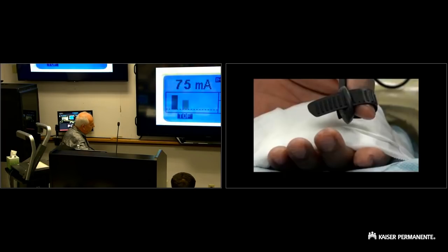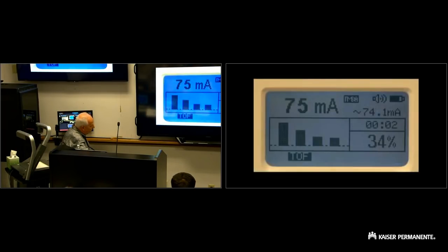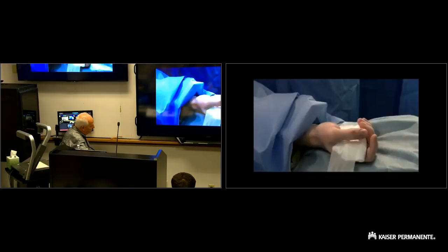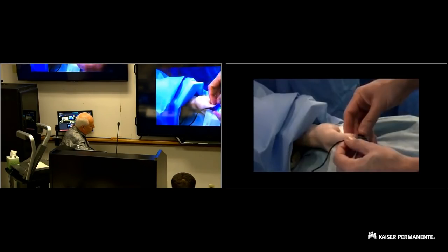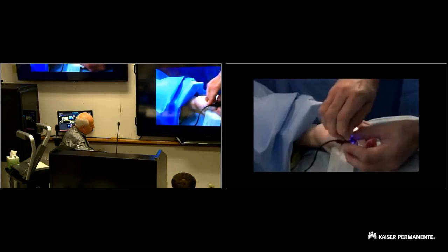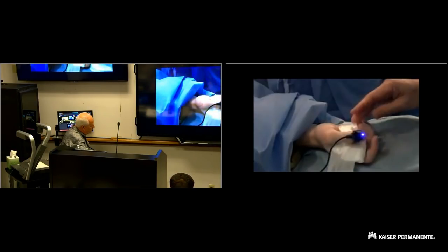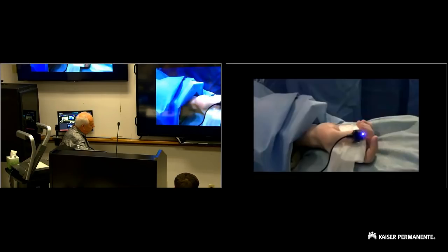In the clinical setting, the tool used most frequently for the objective evaluation of neuromuscular function is acceleromyography. To perform acceleromyography, affix the accelerometer onto a moving digit, ideally the thumb, to measure acceleration in response to ulnar nerve stimulation. It is not difficult to set up an acceleromyography device.